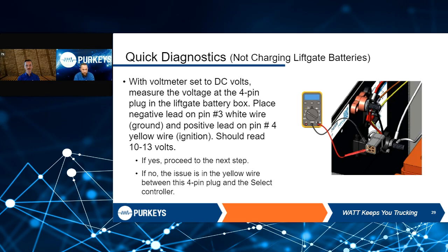Now move over to the voltmeter set to volts: place the negative lead on pin number 3, which is your ground, and the positive lead on pin number 4, which is your ignition. If you have it up front, you want to make sure you have it at the DC-DC converter, because again, that's what's telling that converter to turn on. So if you have voltage, proceed to the next step. If no, again, that issue is in your yellow wire. Either it's a break in that circuit or a loose connection. I've even seen where there was too much heat shrink put on the ring terminal when it was tightened down on the stud, and that was causing the break in that circuit. Just simply too much heat shrink over the eyelet, and it was causing it to make and break contact.